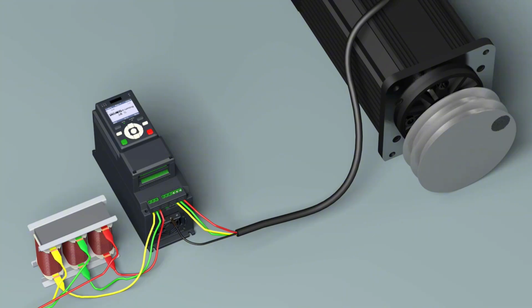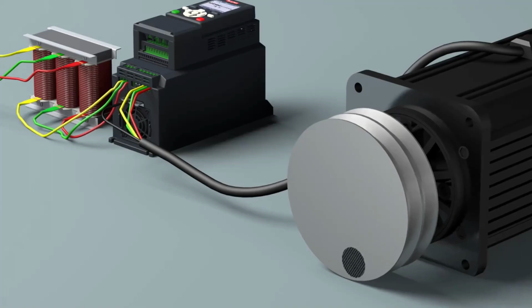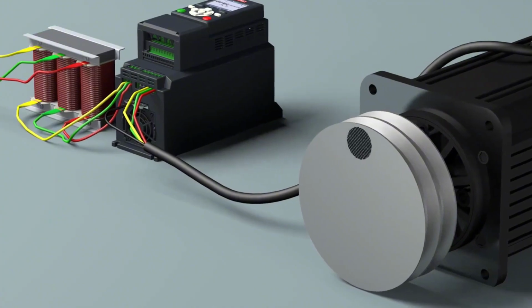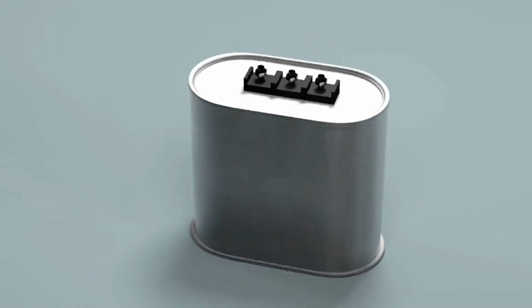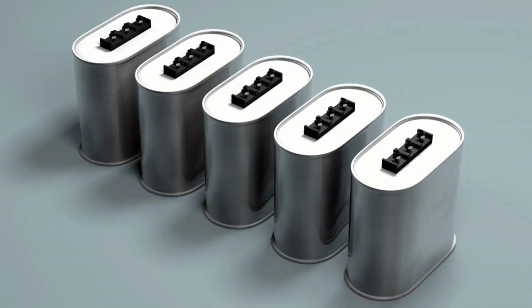3. Inverter and speed regulator protection. Large motors often have reactors placed in front of inverters or speed regulators. Reactors prevent harmful harmonic waves generated by rectifier units from affecting the power grid. Ramp waves can damage power compensation capacitors and lead to inadequate reactive power compensation.